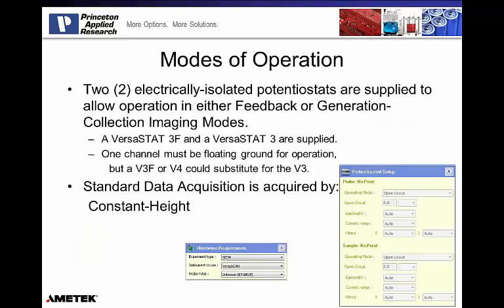So let's talk a little bit about different modes of operation. We're going to come back to this in a summary slide in a couple of slides. But we're going to use two electrically isolated potentiostats. That's going to allow us to operate in either feedback mode or generation collection mode. Feedback mode typically uses a single potentiostat, and it relies on the thermodynamics of your sample to cause the balancing electrochemical reactions that are measured. It's very good for doing approach curves and measuring localized conductivity changes on your sample surface. Generation collection mode has become more popular, and it's very common for sensor or kinetic type applications.